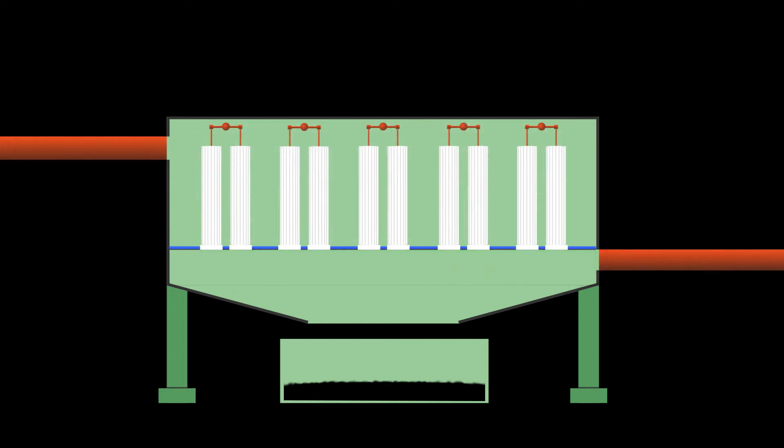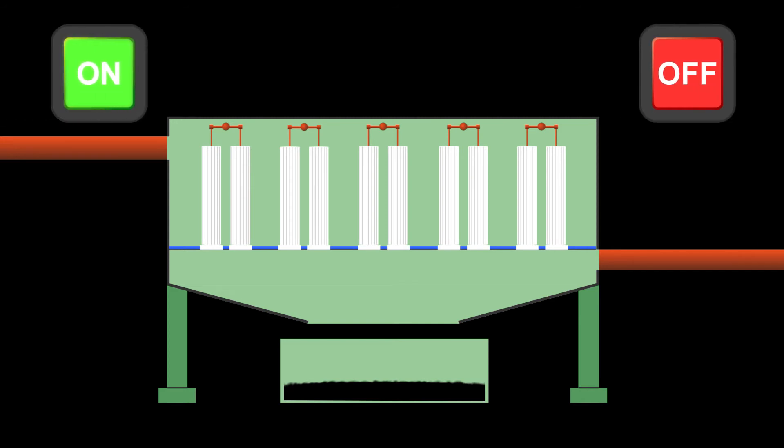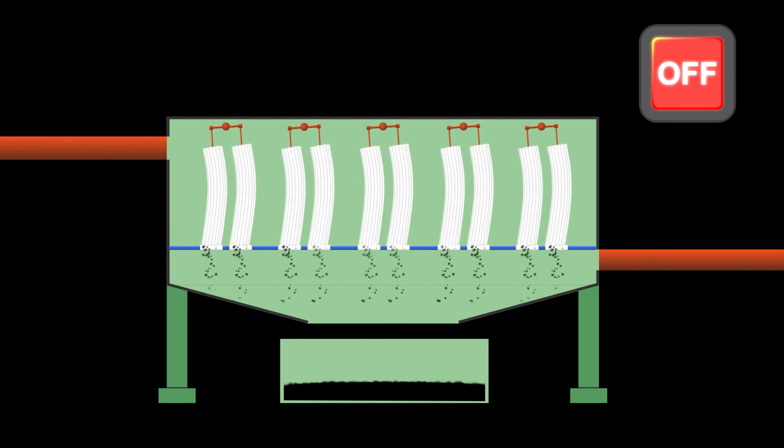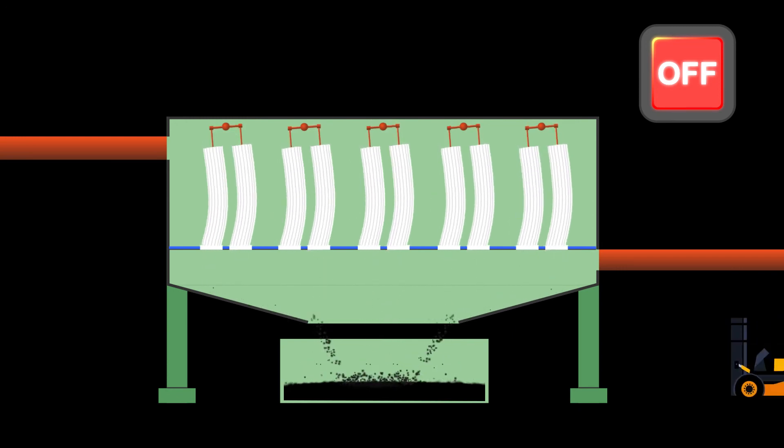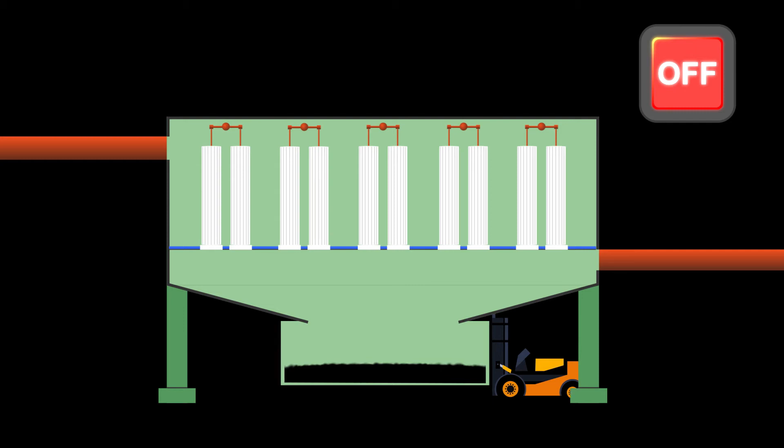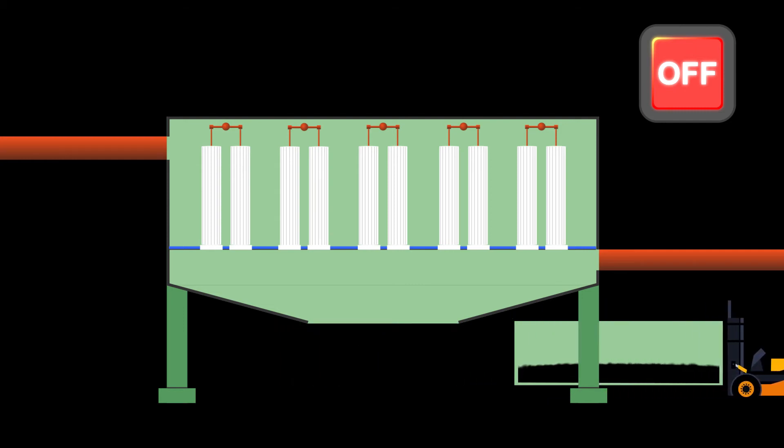To clean a shaker baghouse, which normally uses woven filter bags, the airflow through the system must be periodically shut down, also referred to as being taken offline, while mechanical shake cleaning is employed. After the dust cake is released from the bags, it falls into a hopper at the bottom of the baghouse for removal.